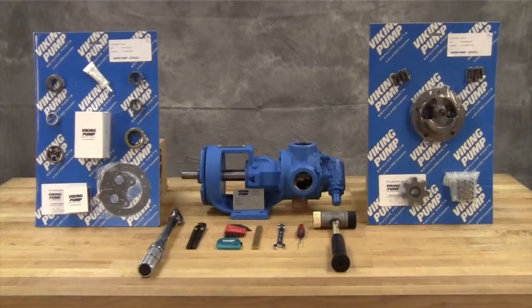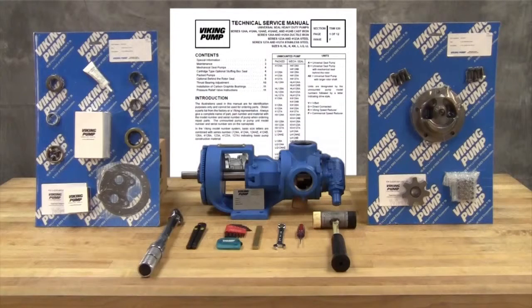You may require the following tools for disassembly and repair: SAE wrenches, Allen wrenches, and a soft-headed hammer. A complete listing of tools and part numbers can be found in the service manual. For newer pumps, seal kit and repair kit part numbers can be found on a hang tag on the pump. For older pumps, or if the tag has been removed, contact your local authorized Viking pump distributor with the model and serial number of the pump to obtain these part kit numbers.